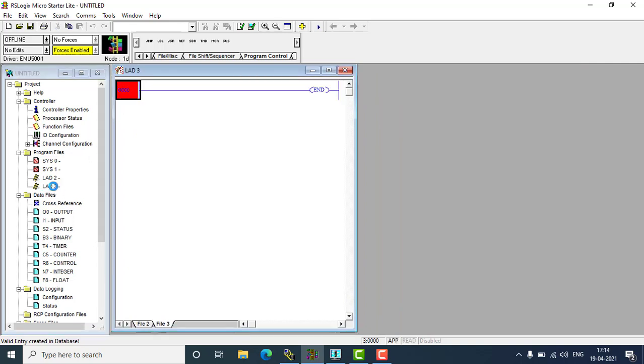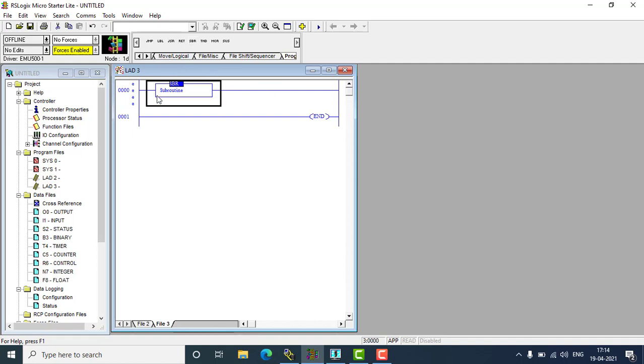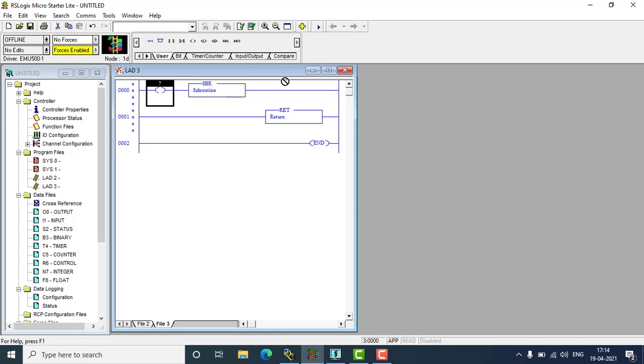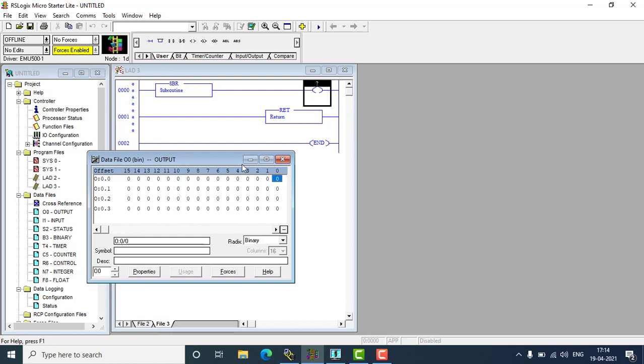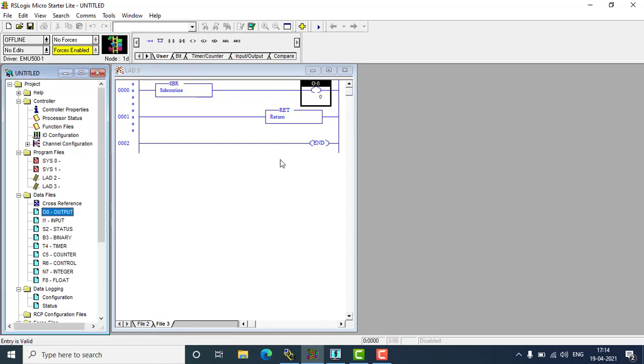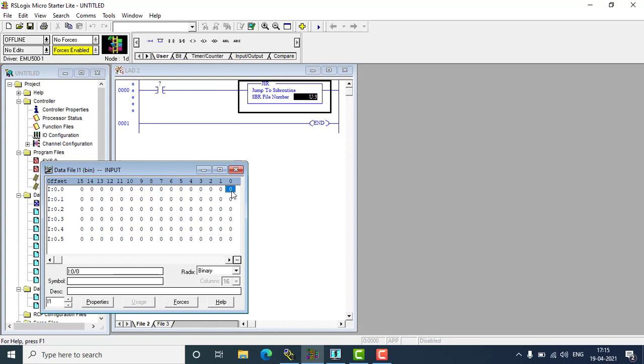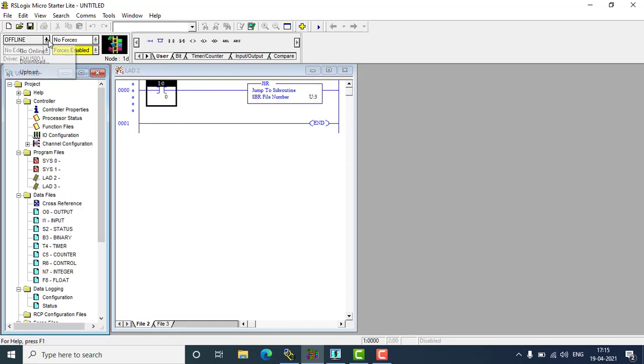That will be enabling the programming in Ladder 3. Now I am at Ladder 3 and I have to use a subroutine label here. After the label I have to use my output and also a subroutine return — that is the syntax. I'm placing one output on the sub program; this will activate the output. Output will be O:0.0. I'm going back to the main program Ladder 2. Here is my Ladder 2 main program. I'm feeding the input with I:0.0, which will enable the sub program.